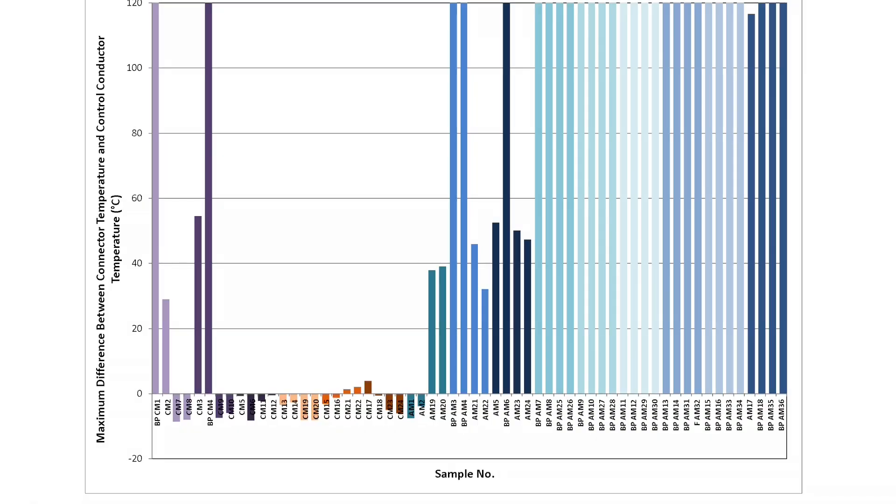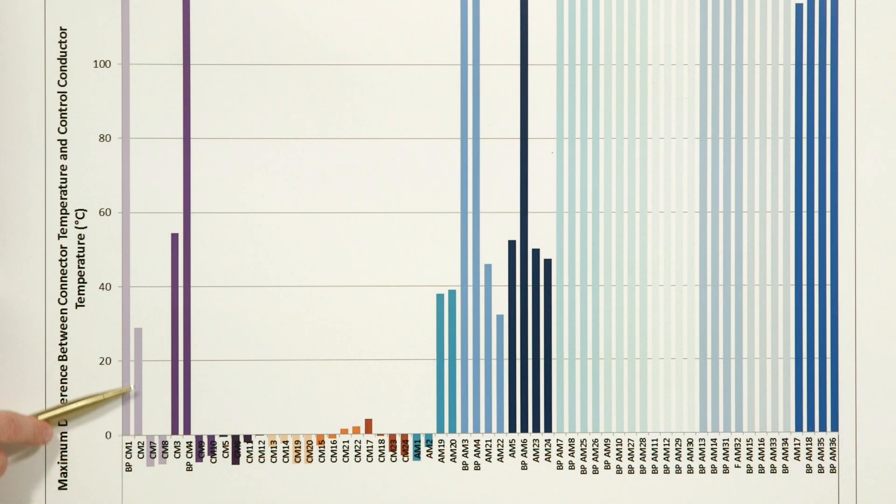This chart shows an evaluation of the temperature after a thousand cycles using the method from the IEC standard. The height of each bar is the maximum temperature difference between the sample and the control conductor throughout the test. A temperature difference greater than zero is considered a failure according to IEC.